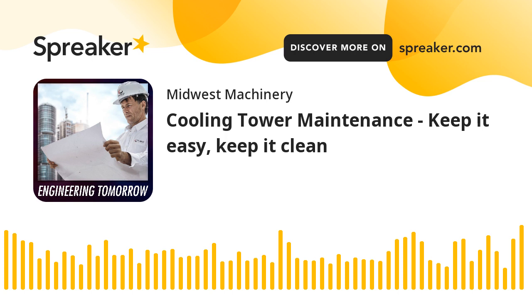So with that said, my favorite part of the show: what is the craziest thing you've seen happen at a cooling tower? There's been quite a few cooling towers where you look in the water and all you see is black. After you see that, you just look at everything else going wrong with the tower — the fill has completely collapsed, the motor isn't working correctly, the fan is shaking so the whole tower looks like it's about to fall over. It's just amazing what poor water treatment can do to your tower.